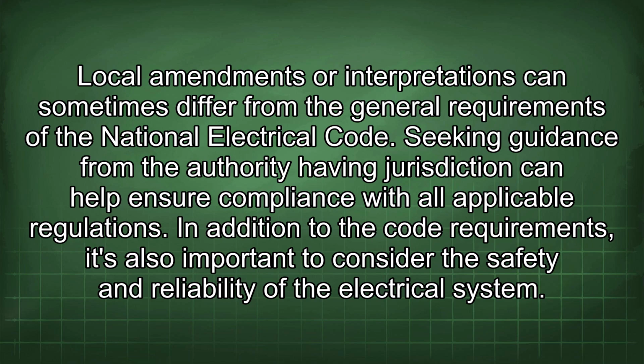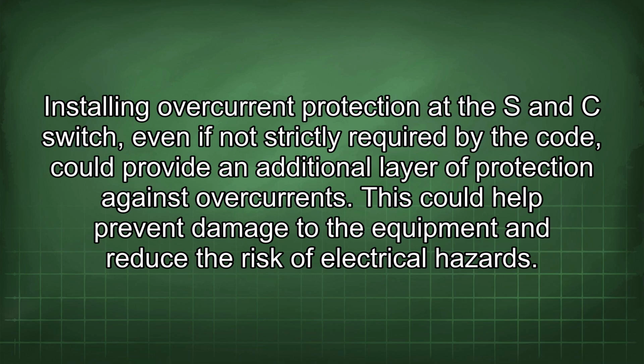Seeking guidance from the authority having jurisdiction can help ensure compliance with all applicable regulations. In addition to the code requirements, it's also important to consider the safety and reliability of the electrical system. Installing overcurrent protection at the S and C switch, even if not strictly required by the code, could provide an additional layer of protection against overcurrents. This could help prevent damage to the equipment and reduce the risk of electrical hazards.